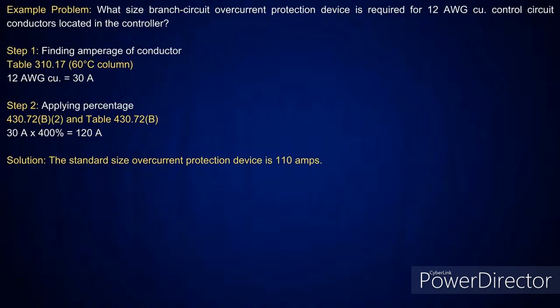So the other thing I'm going to point out, it's also going to tell you that you're going to use a 60-degree C column in this one. When I get to where it goes through the conduit over, then it's going to tell you use the 75-degree C column. So if I go look at table 310.17, pick up a number 12 conductor, it's going to tell you take it at 30 amps. And all I'm doing here is checking the percentage that I'm going to be allowed for the size overcurrent device that's required for the number 12s on those control circuit conductors. So it's going to tell you take it at 400% in table 430.72B. That's going to give you 120 amps. And I said anything over 125%, what do you do? Drop down. So the next size below that is 110 amps, and you'll see that all matches up with sizing the overcurrent protection devices.